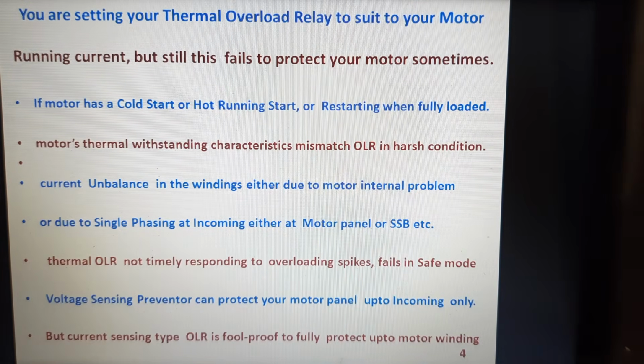You are setting your thermal overload relay to suit your motor running current, and still this fails to protect your motor sometimes. If your motor has a cold start, or a hot running start, or restarting when it is fully loaded, this thermal OLR does not protect your motor sometimes. The motor thermal withstanding conditions mismatch the OLR during harsh ambient conditions. The current unbalance in the windings due to a motor internal problem, or single phasing at the incoming, or either at the motor panel or at the SSB, at that time also this thermal OLR does not protect your motor.